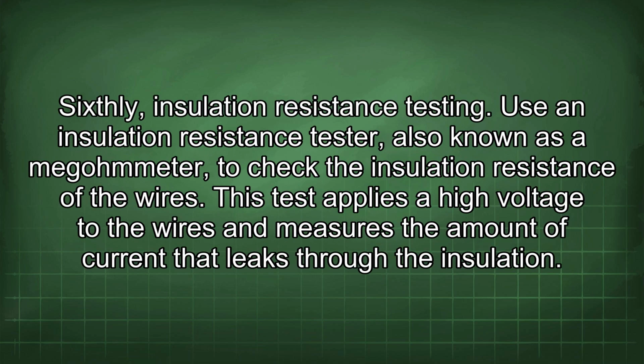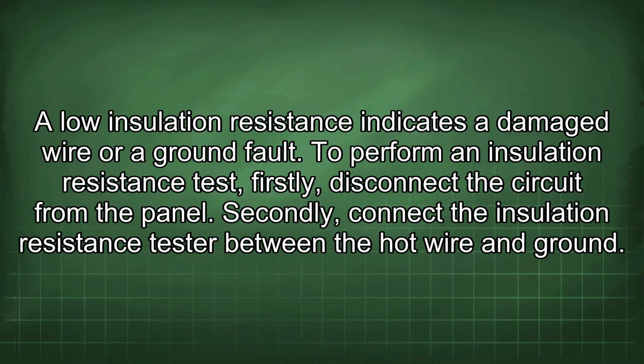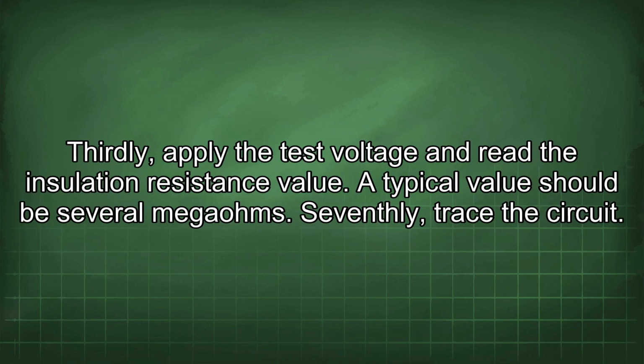Sixthly, insulation resistance testing. Use an insulation resistance tester, also known as a megohmmeter, to check the insulation resistance of the wires. This test applies a high voltage to the wires and measures the amount of current that leaks through the insulation. A low insulation resistance indicates a damaged wire or a ground fault. To perform an insulation resistance test, firstly, disconnect the circuit from the panel. Secondly, connect the insulation resistance tester between the hot wire and ground. Thirdly, apply the test voltage and read the insulation resistance value. A typical value should be several megaohms.